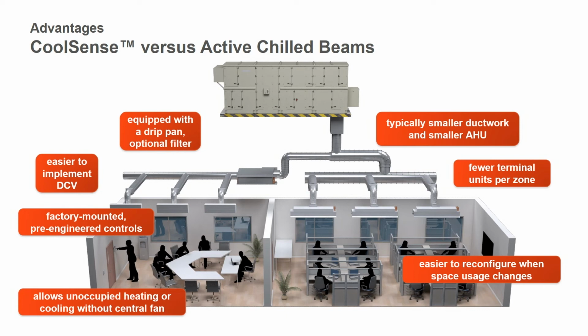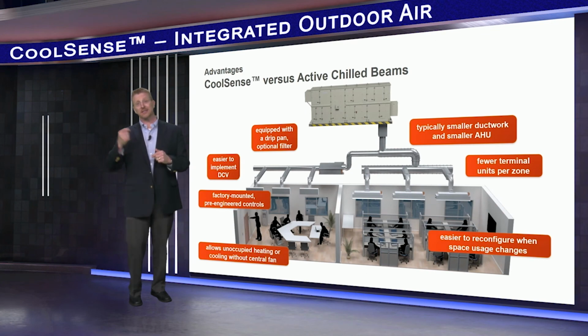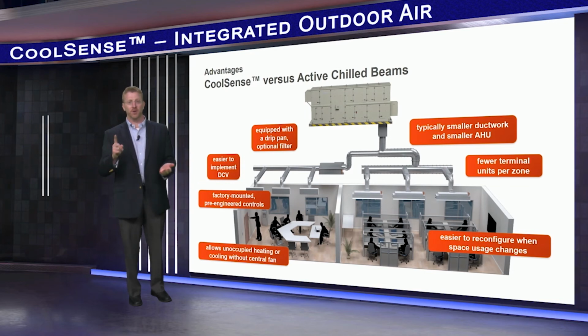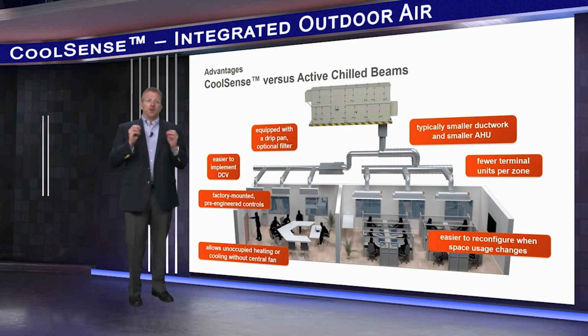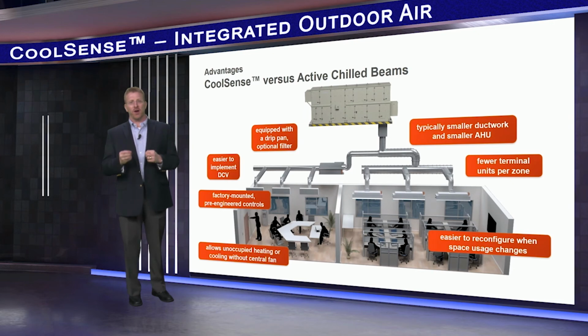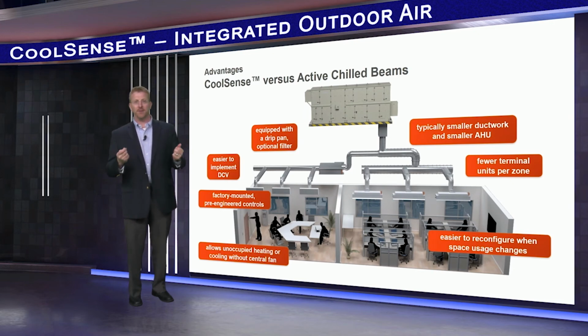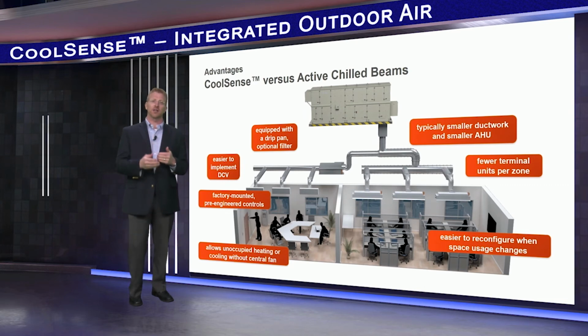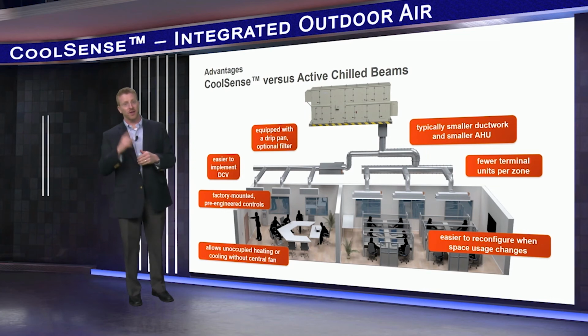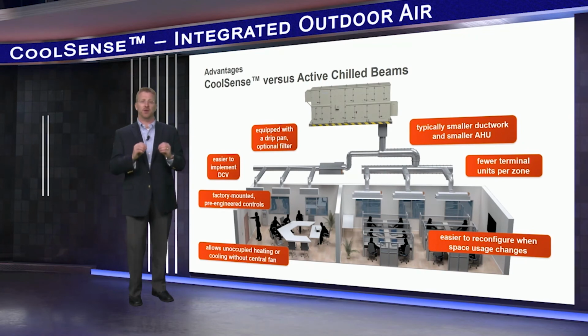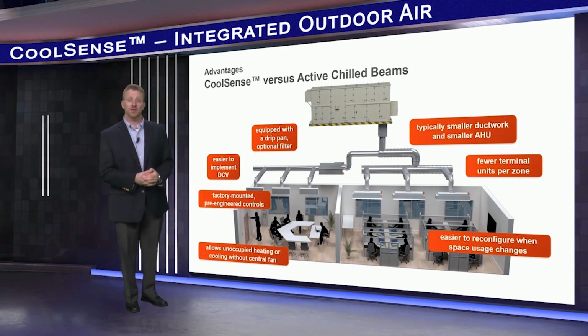Lastly, because CoolSense has a fan, the DOAS or central fan does not need to operate to heat or cool the space. This is an advantage during the unoccupied mode, as only the terminal fan in the zone that requires conditioning needs to operate. The DOAS can remain off, assuming, of course, no dehumidification is needed. In contrast, a chilled beam system always requires the primary air handler to be operating if cooling or heating is needed at any time, occupied or unoccupied, since active chill beams require primary airflow for induction to occur. Further, unless the primary air ductwork is equipped with zone level dampers, the primary air handling unit will supply air to all the zones, even if only a few zones require conditioning. This can be a major source of the energy savings of CoolSense over chill beams. All of this leads to significant savings in first cost, as well as operating costs.